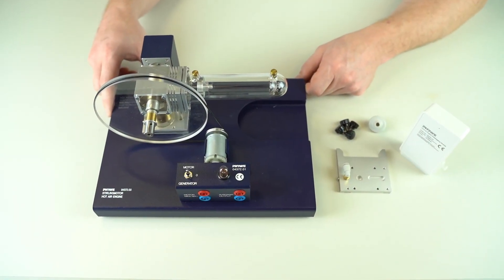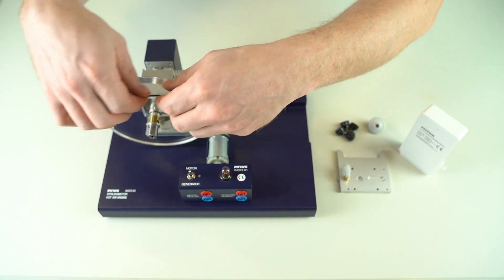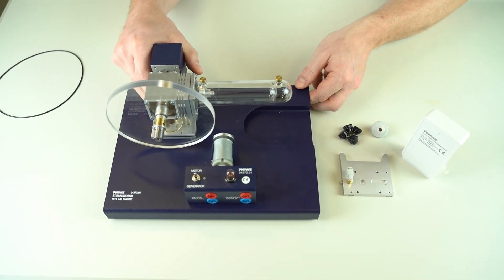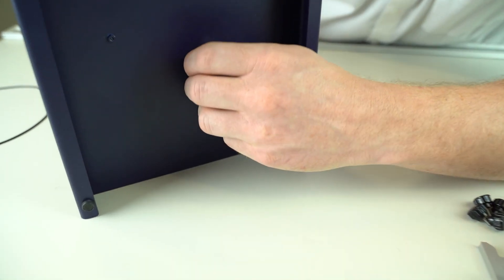In order to get started and to mount the new module we first remove the O-ring and unmount the base plate from the old module by unscrewing it from the bottom.